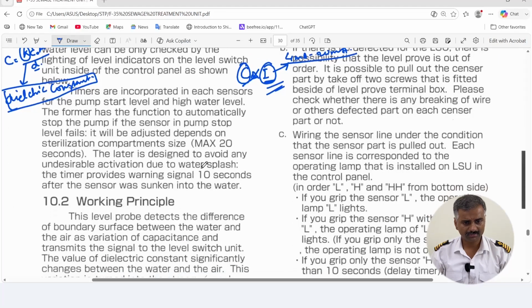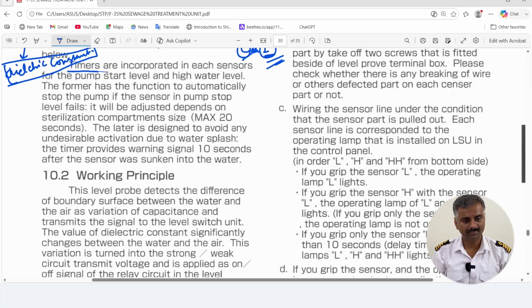Now, timers are there, and these timers are very important in each sensor. Low level, mid level, high level, or high-high level, you have timers according to the sensor. Why is the timer important? You can get a false signal, because this is a level probe. Say in case of rolling or pitching, this is your capacitance level probe, and this is say the low level. In case of rolling and pitching, water goes to this level and then comes down. So due to this sudden change, every time there would be a low level alarm, or say it is reaching the high level, in which case the pump will cut in again and again.